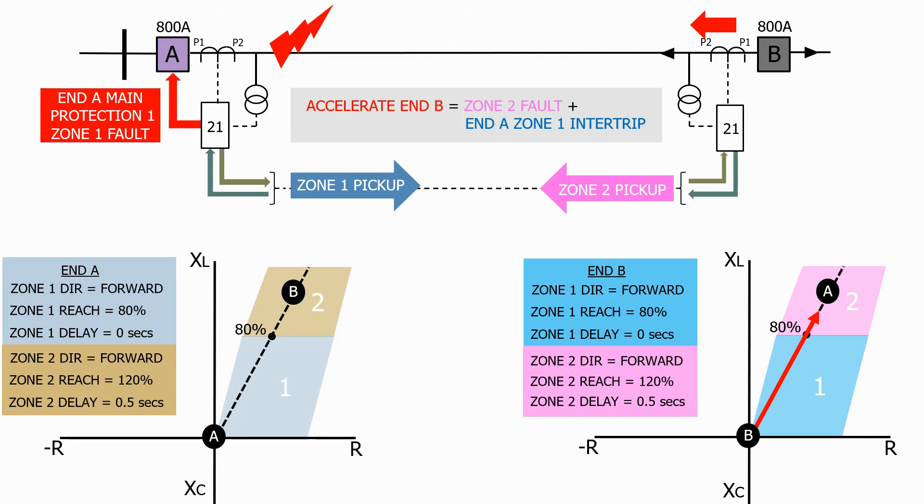On end B the relay sees the fault in zone 2, but because we've received a zone 1 pickup intertrip from the far end, we don't wait for the usual half a second but instead trip the circuit breaker on end B instantaneously as we're now 100% certain that the fault is located on the protected feeder, clearing the fault from the system.